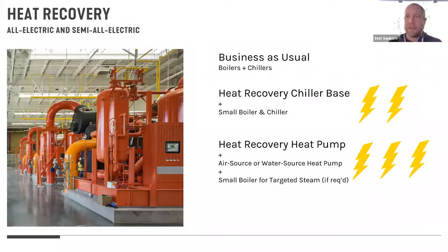Now, on the larger scale projects, we have more and more of that simultaneous demand, especially when we start layering on different building types. If we have a campus where we have a lab plus an office, administrative wing, and maybe an educational classroom, those load profiles, when we stack them up, provide a really nice heat recovery opportunity. It's when we have all the same type of building and we're stacking all of them up together that we don't get as much overlap. We start to get a lot more asymmetry and you might be relying more on your boilers or auxiliary chillers.